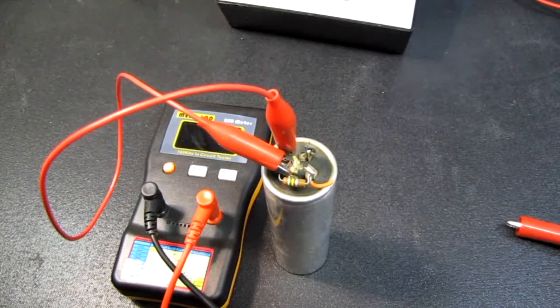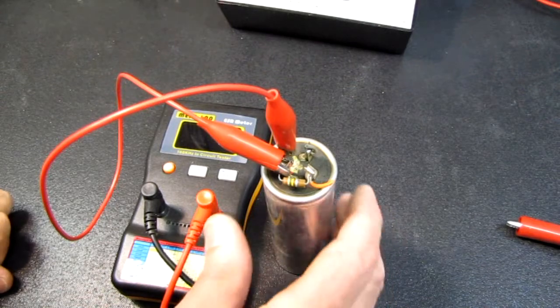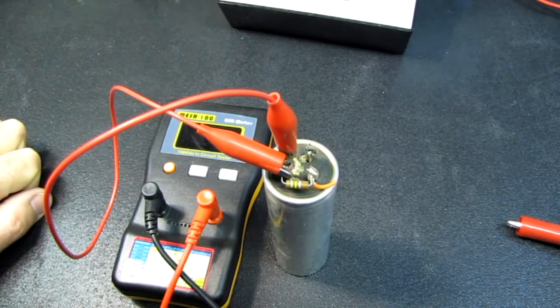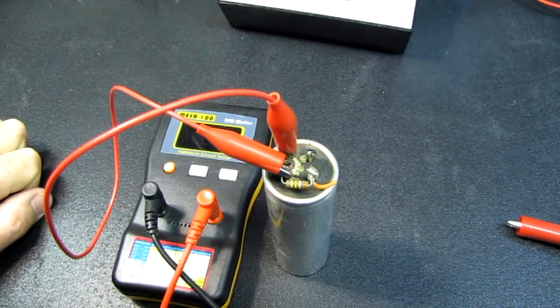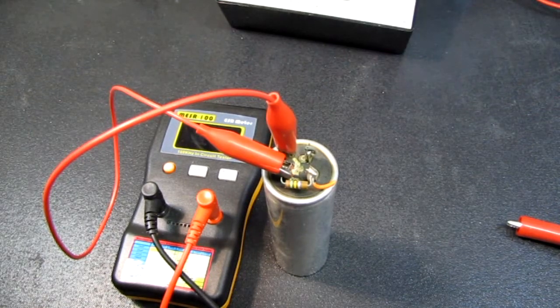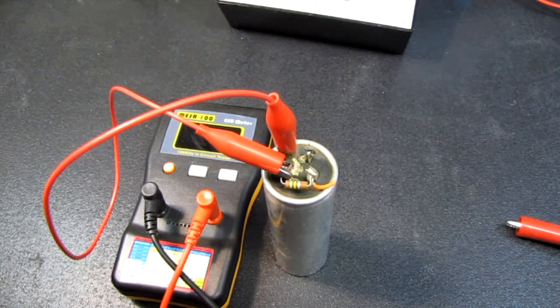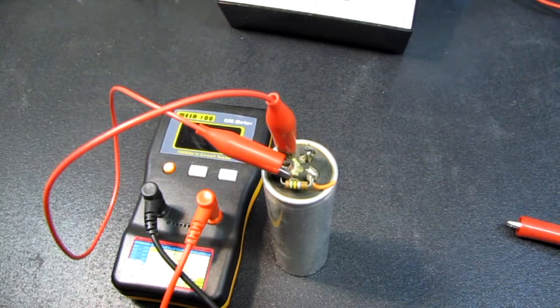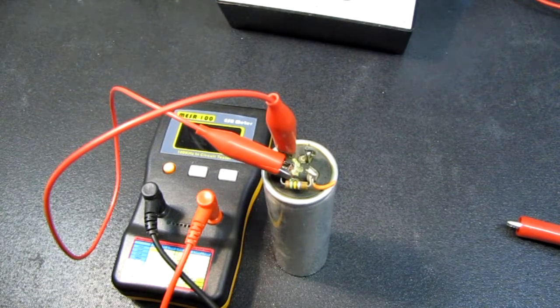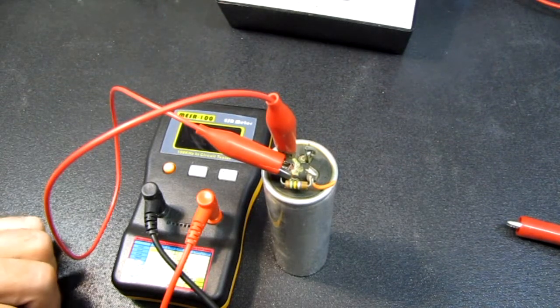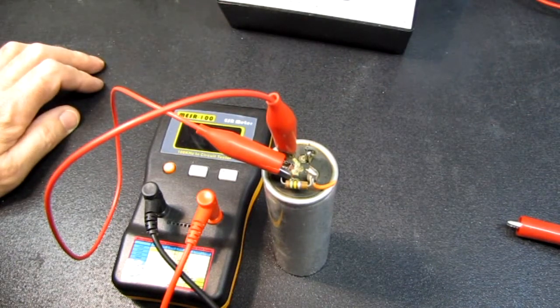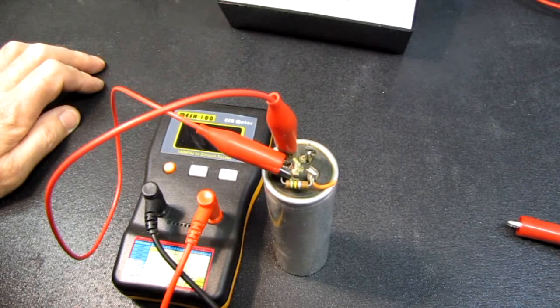Okay, so we've discharged the cap and we've let it sit here for a couple of minutes with a shorting bar or a shorting jumper on it. And the reason I've done that is you'll find these capacitors, if you discharge them with a resistor or even a screwdriver and you come back a couple minutes later, you'll get another spark out of them. You come back a few minutes after that, you'll get another spark out of them. It's a known effect with big electrolytics that they will rebuild some of the charge. And that's why you see these great big oil filled high voltage capacitors, they always have a shorting wire across them. Because if they've been charged and yet they're disconnected, they can build up a good portion of that charge again. It won't have as big a current hit, but they can build up to many thousands of volts in some of those big capacitors.